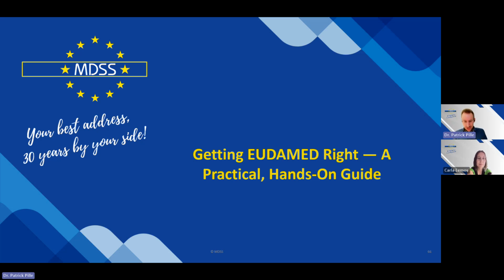The discard function is only possible until the UDI-DI is linked to another element in EUDAMED. For now, the only way this could happen is when the device, the Basic UDI-DI, is linked to a product certificate in EUDAMED. Once that is done, it can't be discarded. And later, once the vigilance module comes into play, somewhere next year, it's not yet defined when exactly, a device registration linked to an incident report within EUDAMED will also not be discardable. So for now, the recommendation is, of course, to check the information before submitting, right?